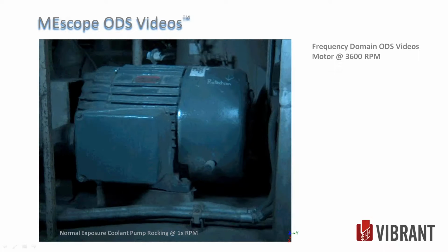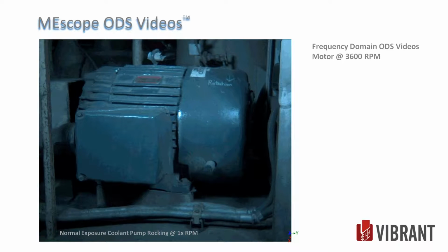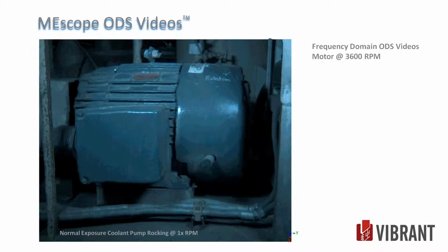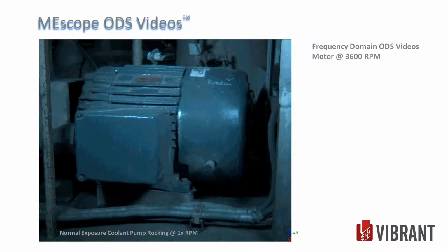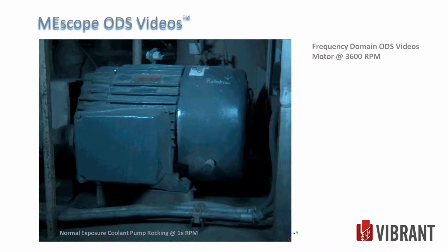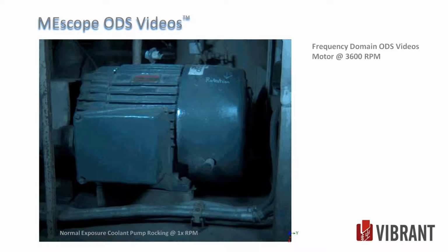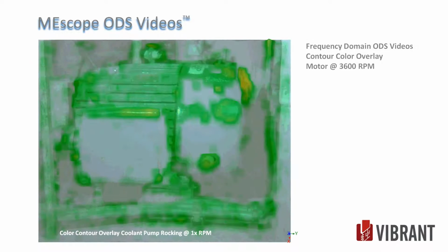This is one of the ones I wanted to show you because we could barely get a good angle to see what's going on. It also had a rocking motion. And so the first couple slides here are showing us that tipping motion of the motor, very similar to what we saw in the other sister unit. And that's all at turning speed of the shaft, 3,600.